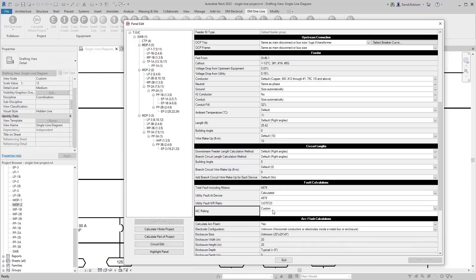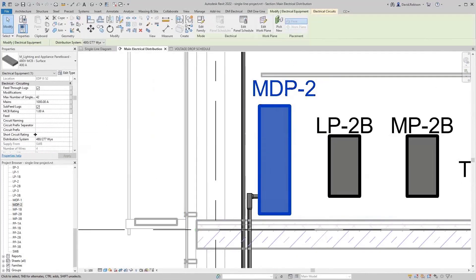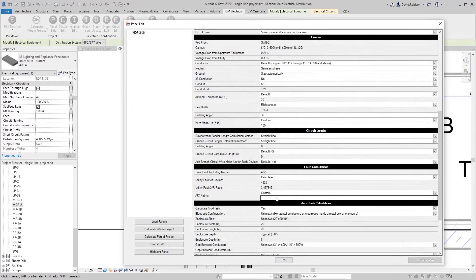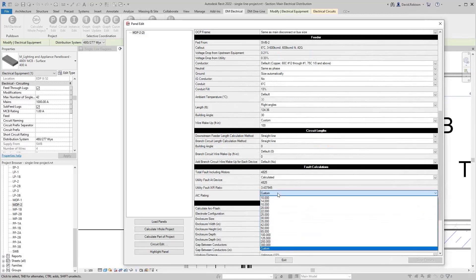The AIC rating links to what Revit calls the short circuit rating. You put the value in and it fills in that Revit parameter. We intentionally don't automatically choose this value — since AIC rating has a huge impact on the cost of your panel and involves fire safety considerations, we want the engineer to specifically think about and choose the right value. So we calculate the fault, and then you manually set the AIC rating for that panel.